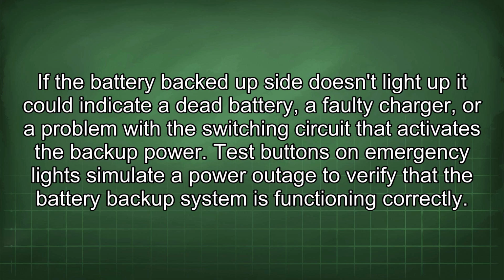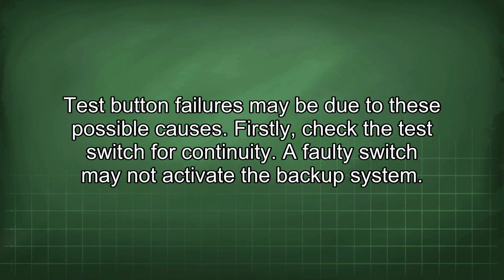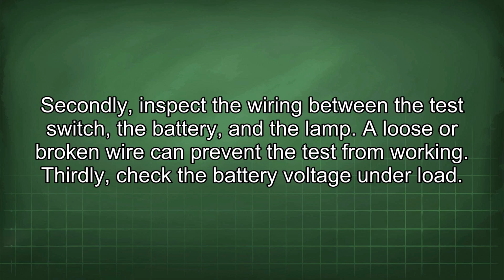Test buttons on emergency lights simulate a power outage to verify that the battery backup system is functioning correctly. Test button failures may be due to these possible causes. Firstly, check the test switch for continuity. A faulty switch may not activate the backup system. Secondly, inspect the wiring between the test switch, the battery, and the lamp. A loose or broken wire can prevent the test from working.